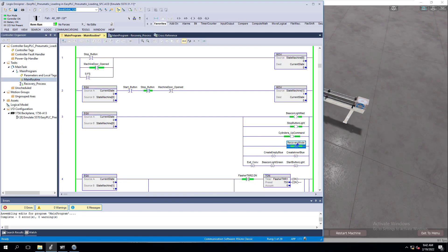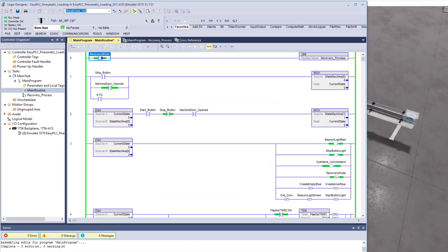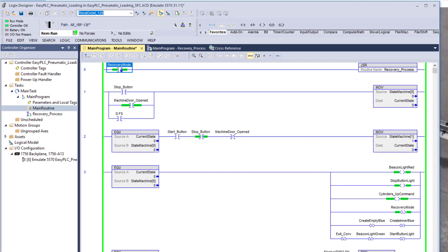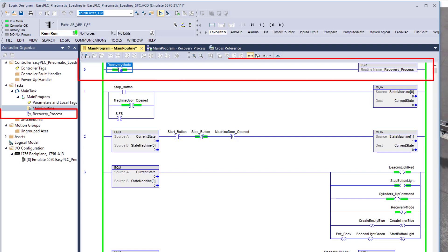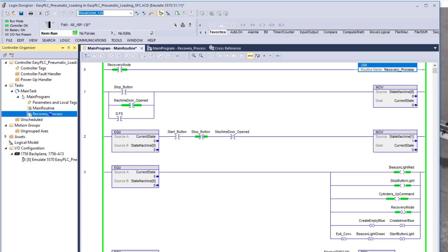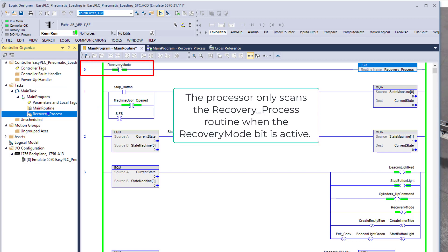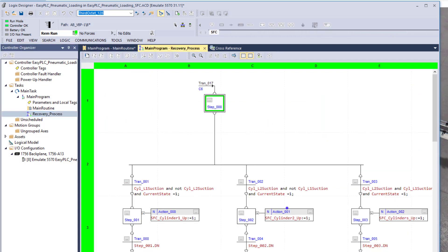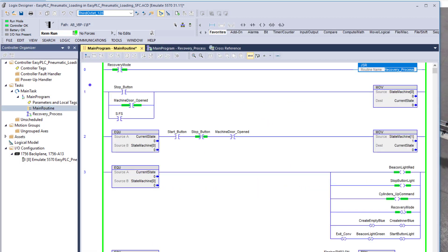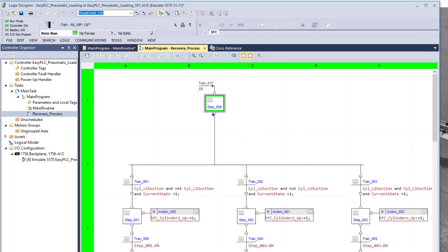We've come over here and activated our recovery mode. Our recovery mode is triggering a bit — just a binary bit that goes active. As soon as the bit goes active, it triggers a JSR, which then starts scanning, allowing the PLC processor to start scanning the recovery process right here, which is going to be our sequential function chart. If the machine is in normal mode, it won't actually scan this routine. This recovery process routine is not going to scan until that one bit — called recovery mode — is actually active.